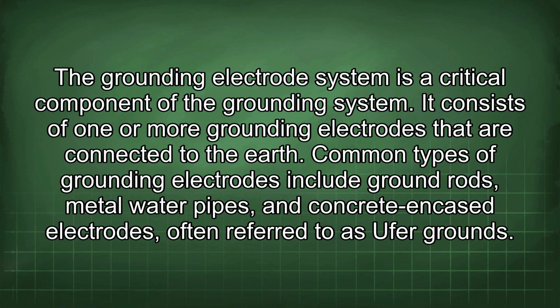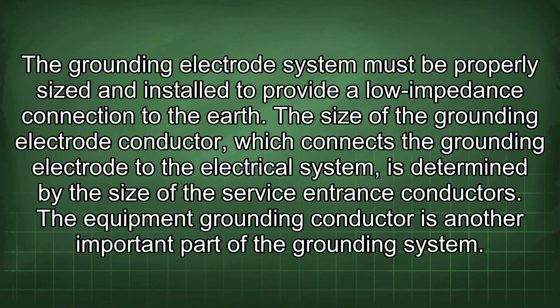The grounding electrode system is a critical component of the grounding system. It consists of one or more grounding electrodes that are connected to the earth. Common types of grounding electrodes include ground rods, metal water pipes, and concrete encased electrodes, often referred to as Ufer grounds. The grounding electrode system must be properly sized and installed to provide a low impedance connection to the earth. The size of the grounding electrode conductor, which connects the grounding electrode to the electrical system, is determined by the size of the service entrance conductors.